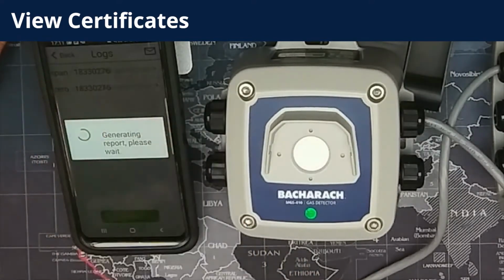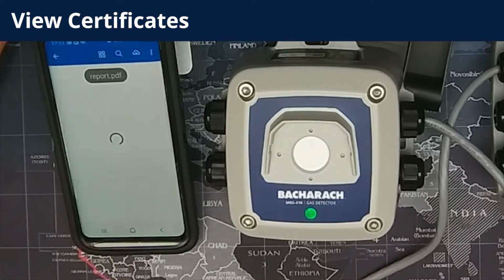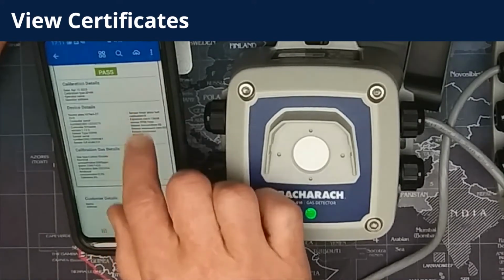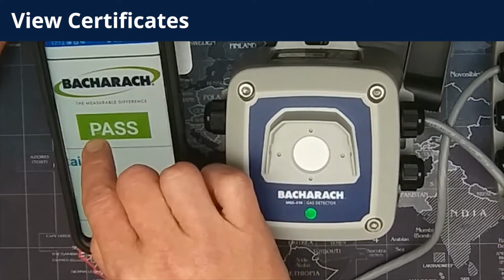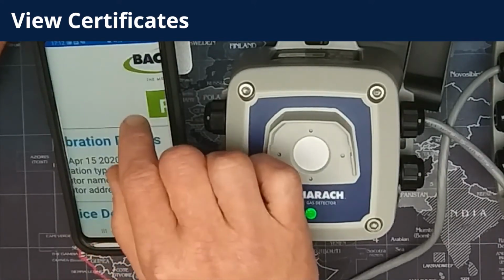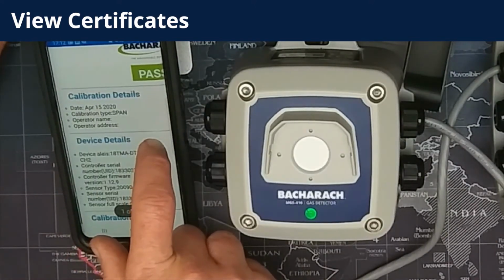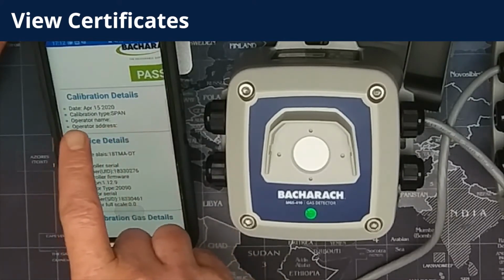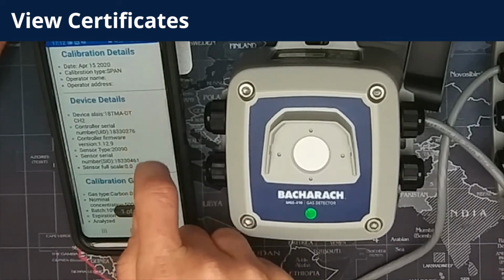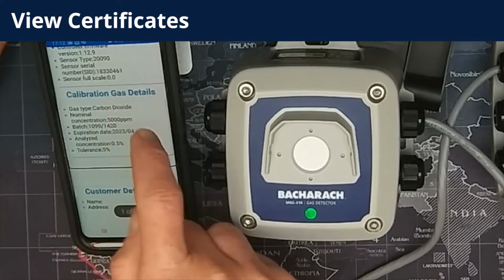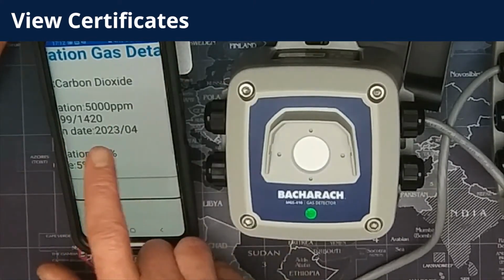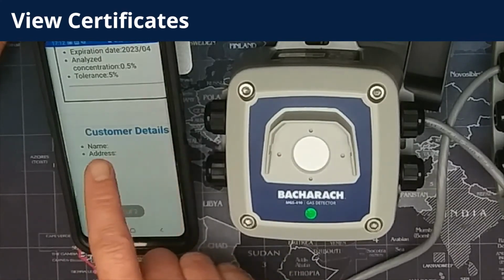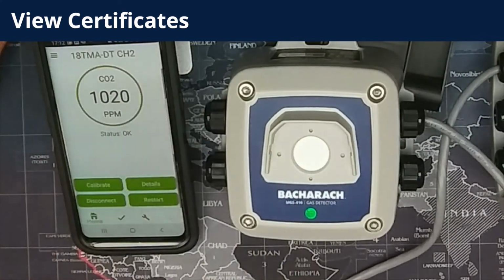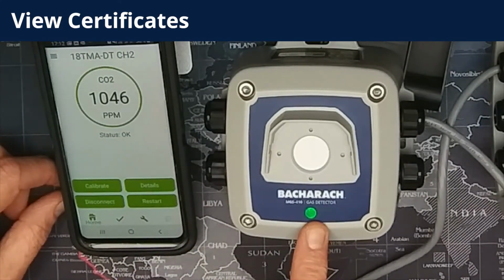So let's take a look at the span certificate now. Very similar in detail, of course, but this is for the span calibration. So there is two, one for the zero and one for the span. And again, you can customize that logo by entering your own logo file so that it is your company's logo at the top of the certificate. Again, all the details of the device, the calibration, the gases used, and the results are stored within this PDF file. And that PDF file can then be emailed to your office, emailed to the customer, stored for reference. And that's the calibration process complete, with the certificates completed also.